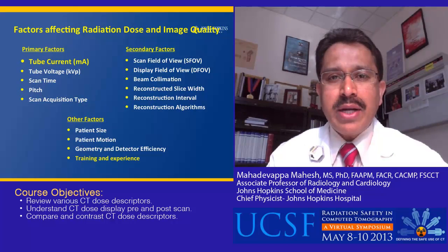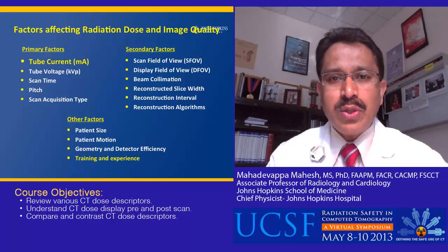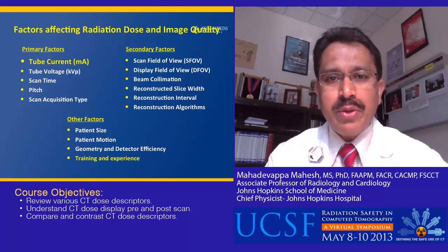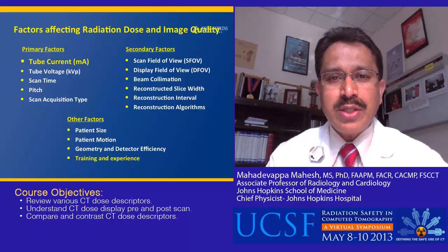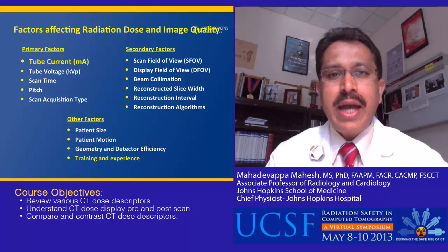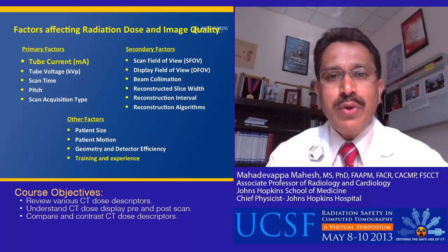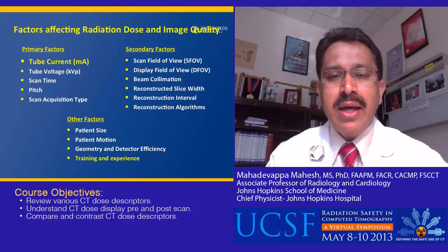Before going into the details of understanding the dose display, it is important to understand some of the factors that influence radiation dose and image quality. Among these, we can look at three different groups: primary, secondary, and other. Primary factors such as tube current, tube voltage, pitch, image acquisition, and scan time have a direct impact on radiation dose and image quality. Secondary factors such as reconstruction algorithms, display field of view, and scan field of view have an impact on image quality directly, and in some way also have an impact due to radiation dose effects.